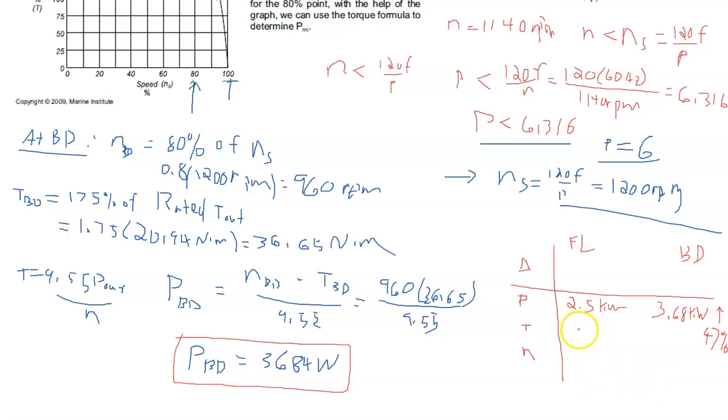For the torque, we know that we went from 100% to 175%, and so that was an increase of 75%. For the speed, we went from 1140 down to 960, and that was a decrease, if we compare it to Ns, of 15%.